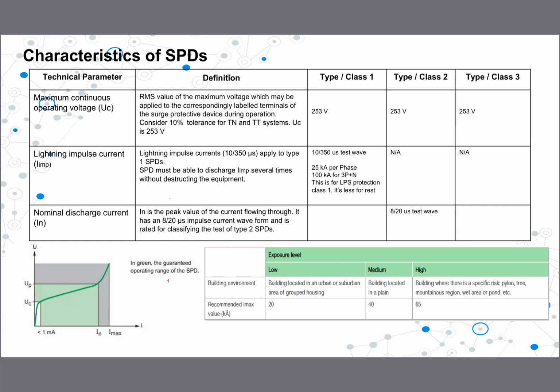And we have 3 types of SPDs: type 1, type 2, type 3. At the entry point, we normally have to install type 1 SPDs. Type 1 SPDs mostly look after lightning discharge currents. Then type 2 SPDs we install at MDB level, type 3 at SDB level, for indirect lightning and switching surges. So based on that, we decide what type of SPD it is, what the class is, and what the technical parameters are.